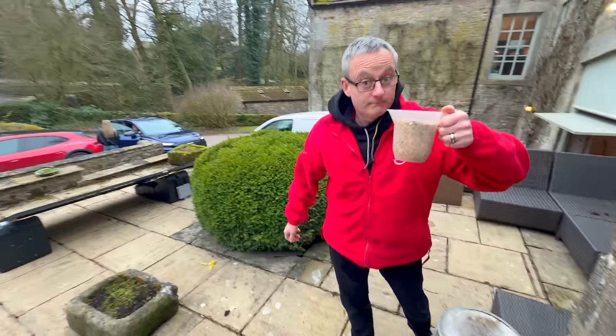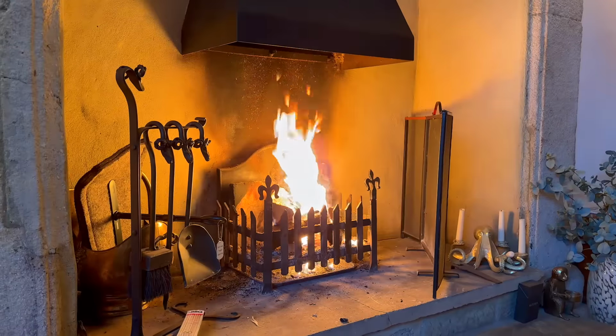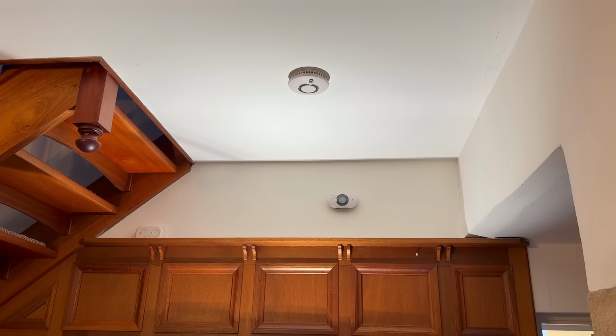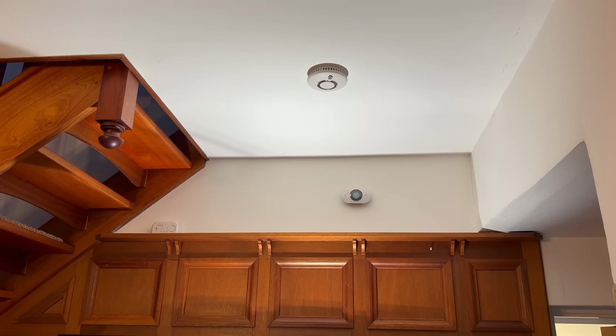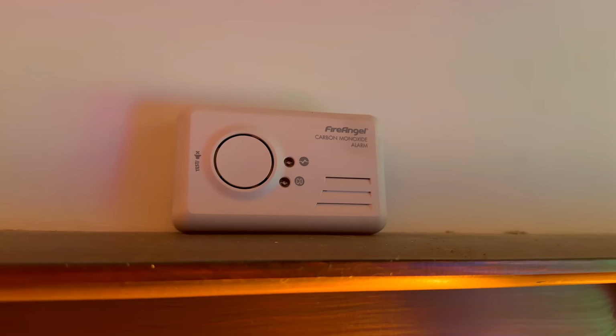This quaint little property in North Yorkshire with its resident ducks has a problem. It's a rental, it's old, and the landlord, like lots of landlords, wants to spend the least amount of cash on maintenance. That is no excuse, by the way. Anyway, at the start of the tenancy the detectors installed are far from ideal. They are also battery only, so what we would identify as a grade F1.